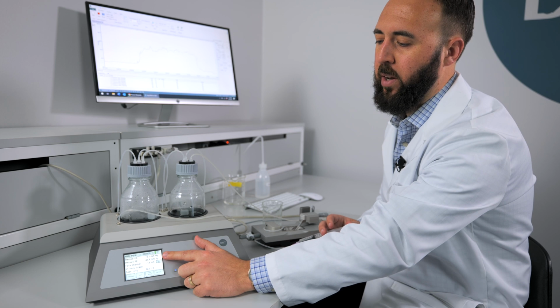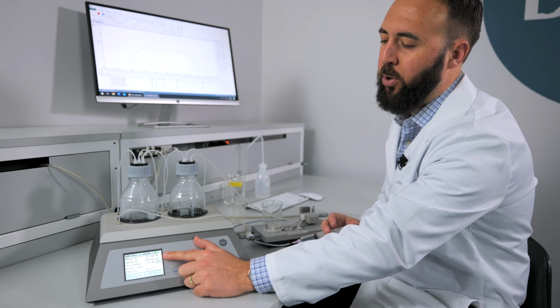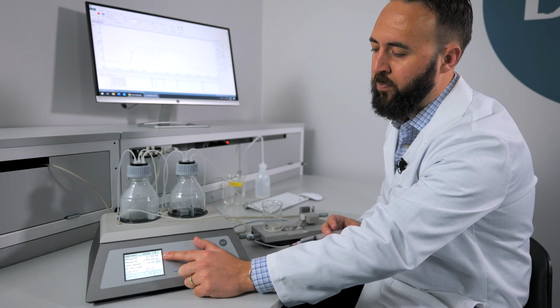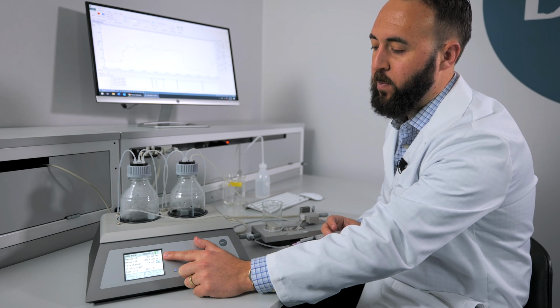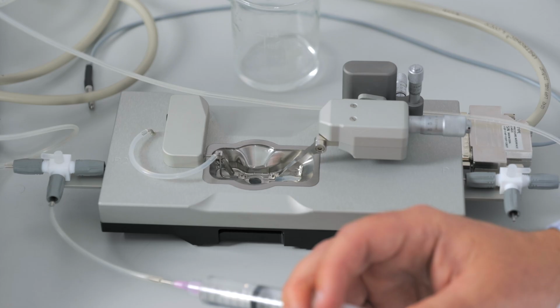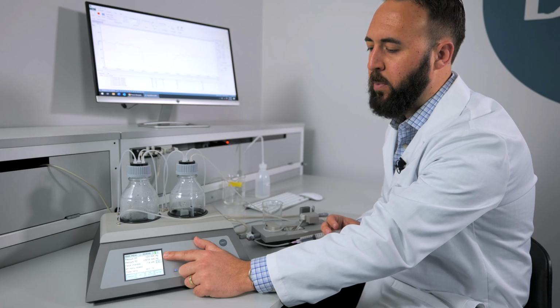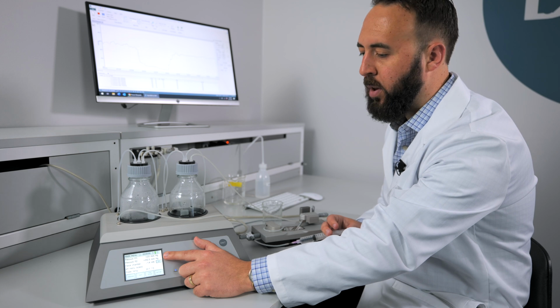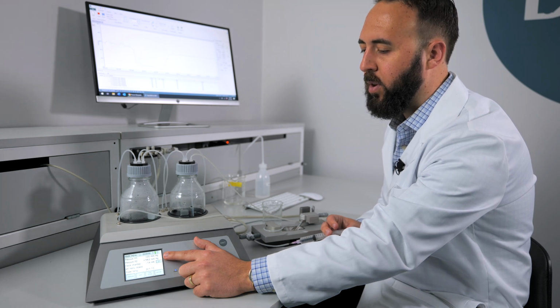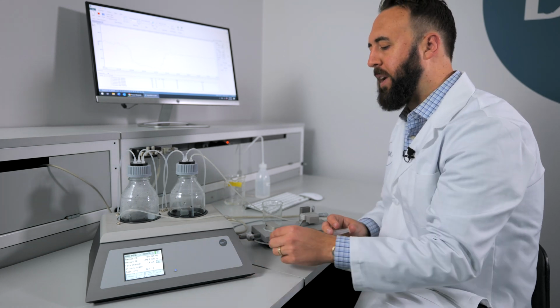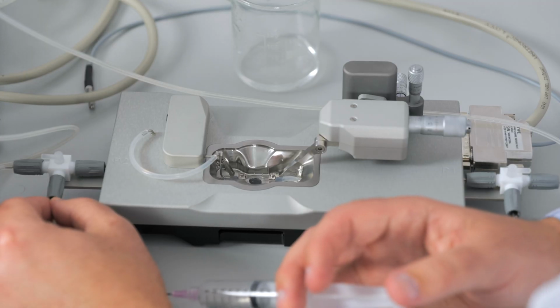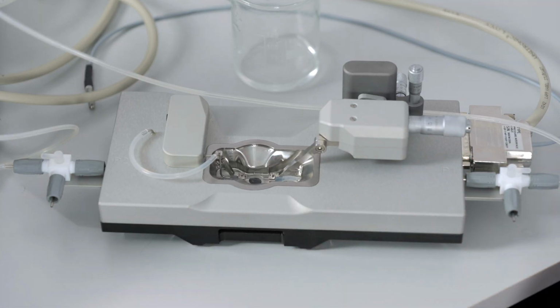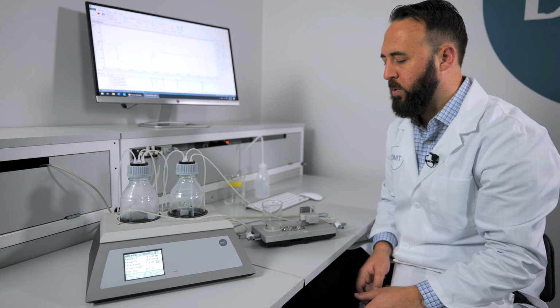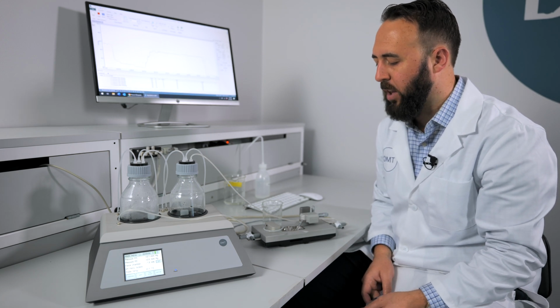Again, now we are looking at the pressure reading for the P2 transducer. We do not want to exceed 200 and especially 250. Again, 1 mil should be more than enough. But make sure that you repeat the process with double distilled water multiple times after you do this to ensure that you don't have acid left in the lines.